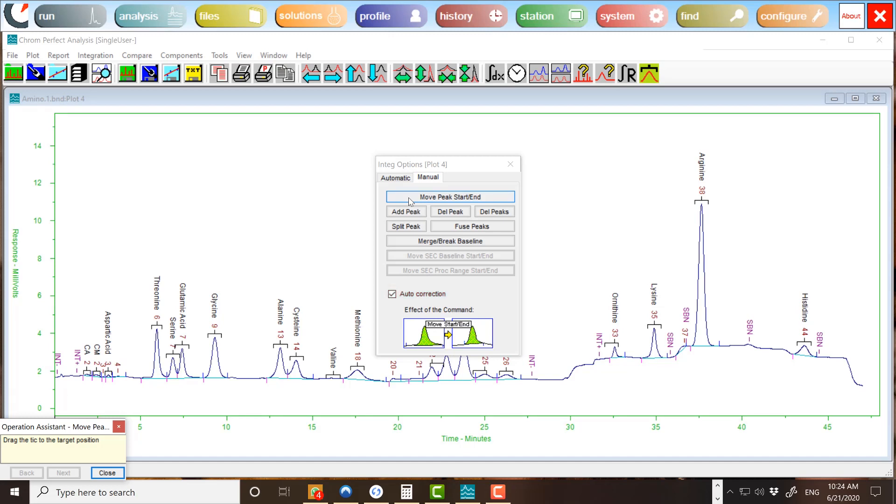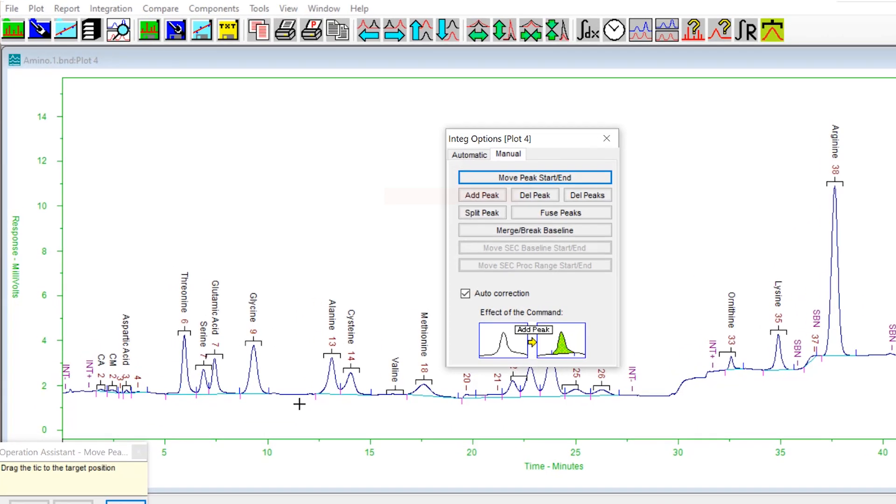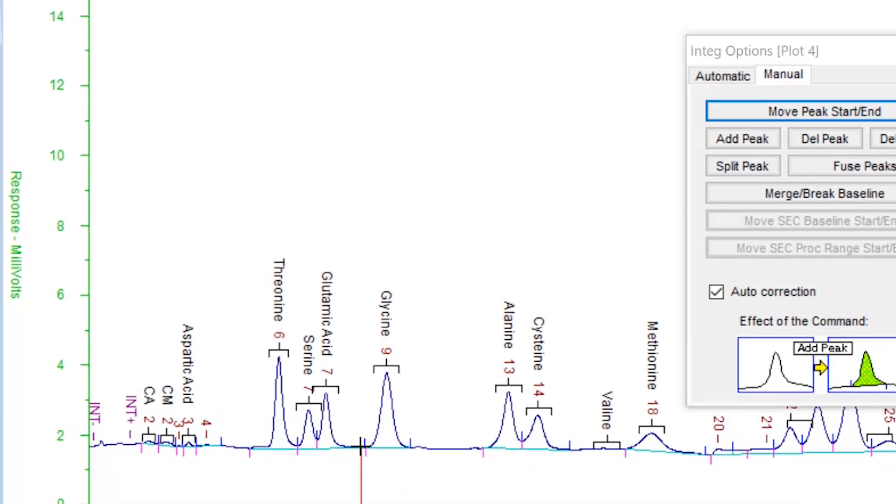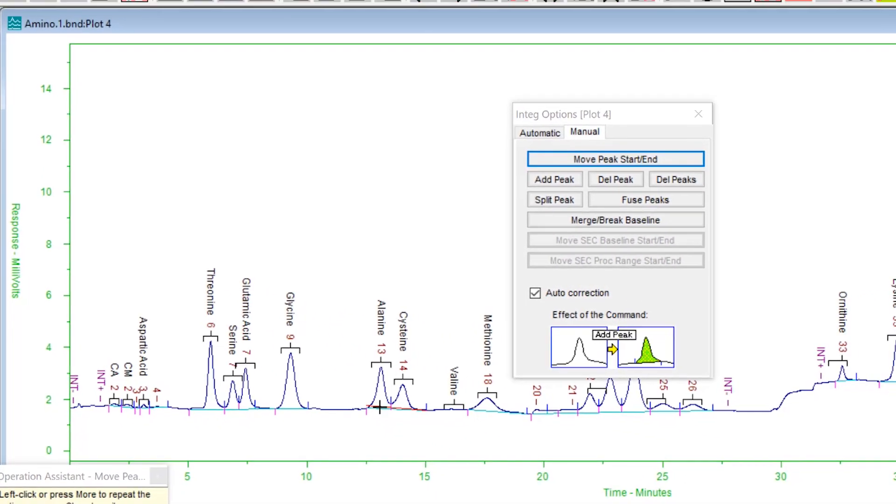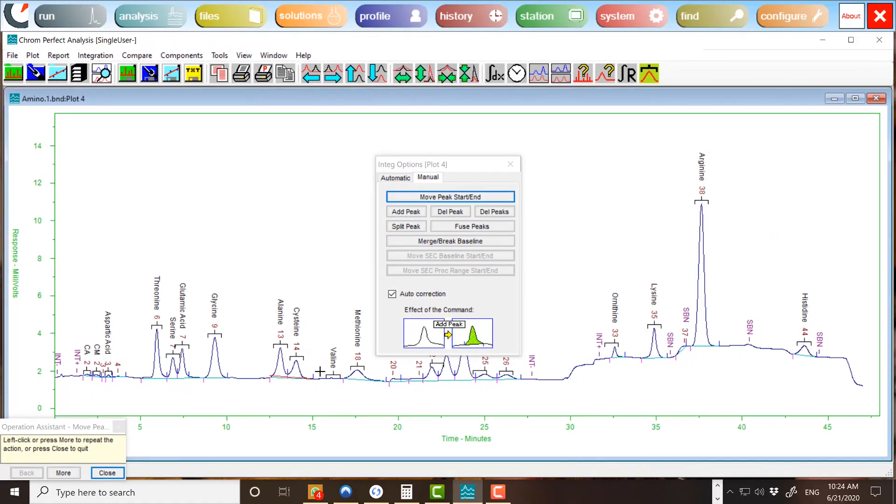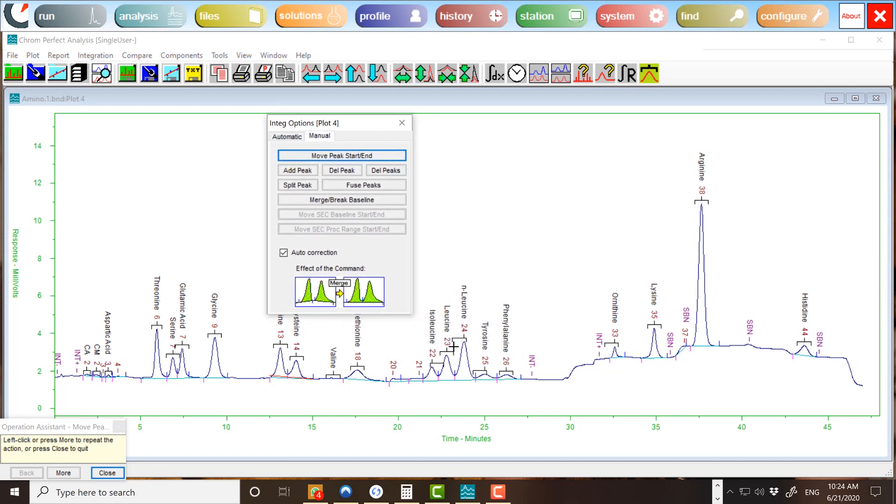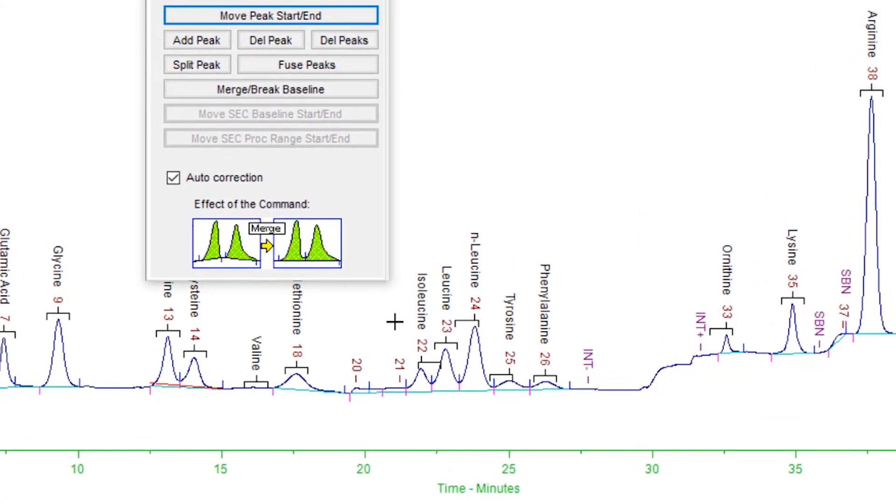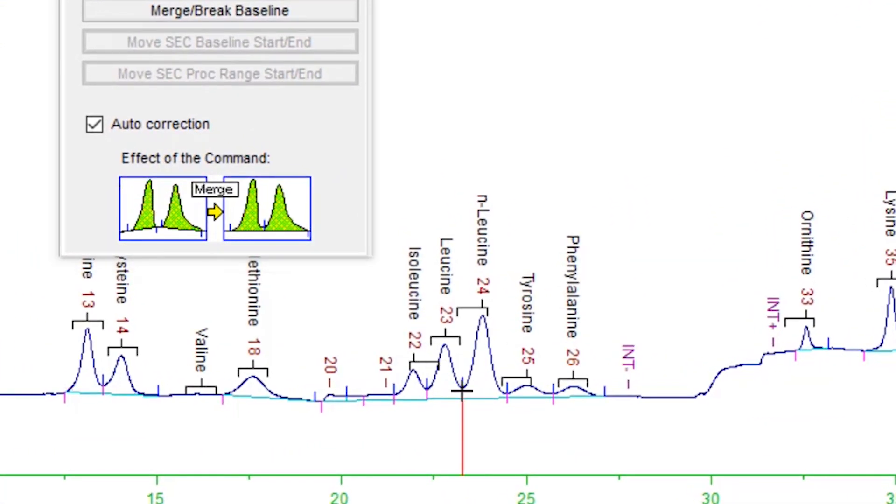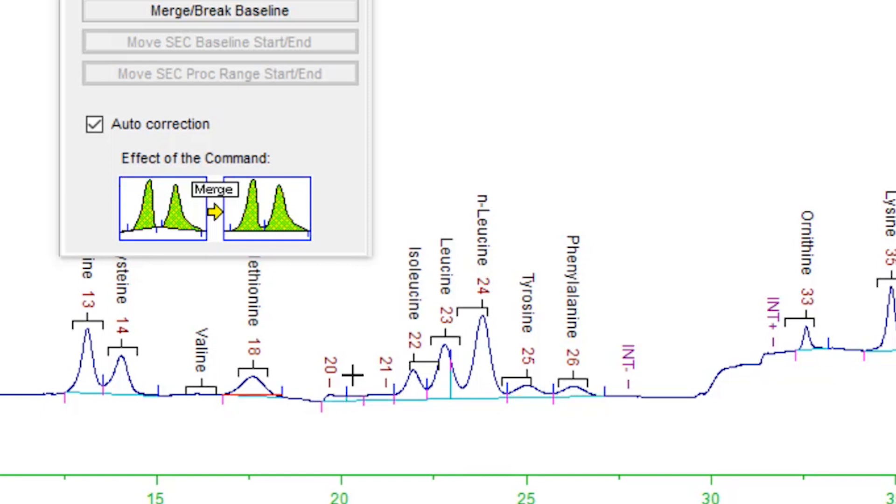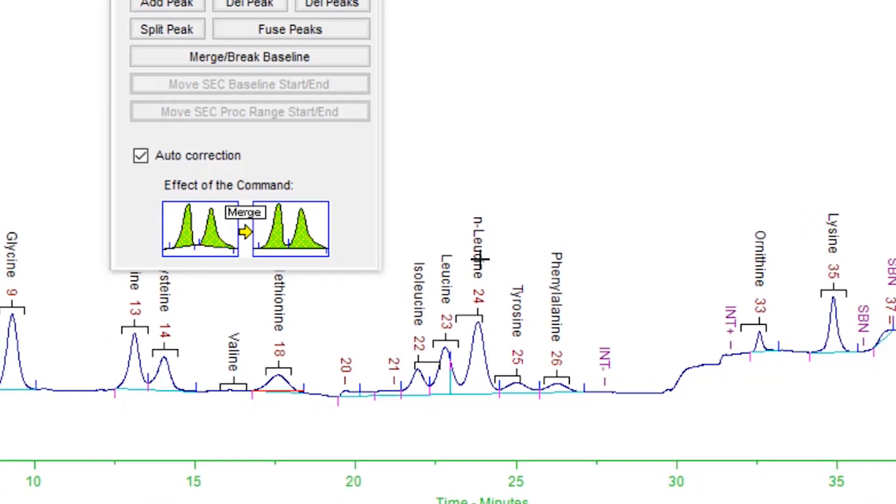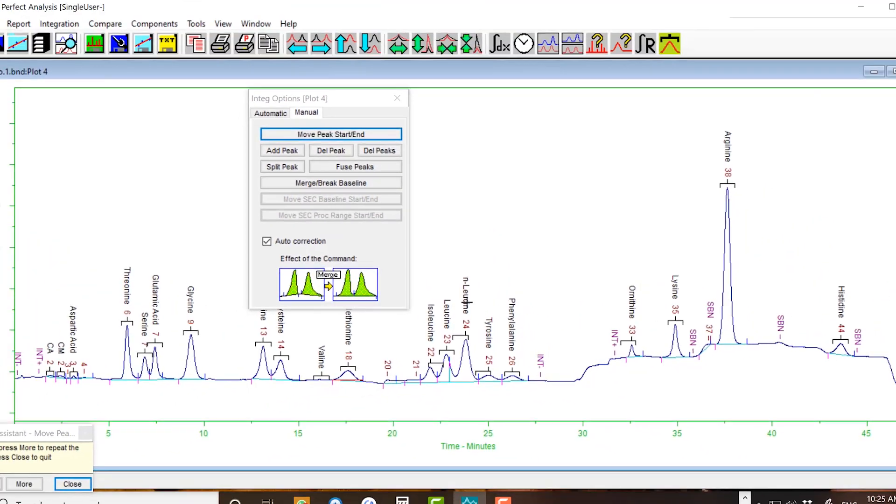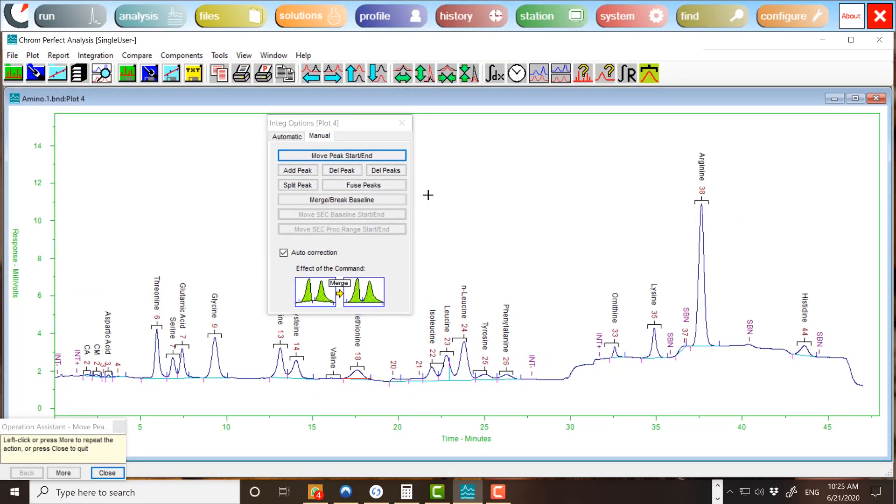To move the Peak Start or End point, press the Move Peak Start or End button. The Operation Assistant will appear, directing you to drag the baseline, actually the tick mark, with the mouse. Click on the chromatogram plot near the baseline of interest. The nearest tick mark will be selected. This tick mark may be external, the start or end of a baseline, or internal, at a dropline. If the tick mark is external, then clicking will grab the baseline. A red rubber baseline will appear. If the tick mark is internal, then clicking will grab the dropline. A red vertical line will appear. You can drag these lines to the desired position and right-click on the chromatogram plot to confirm. The chromatogram will be reintegrated with your new baseline.